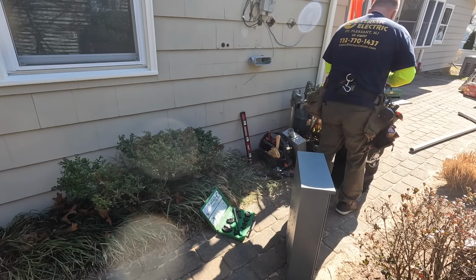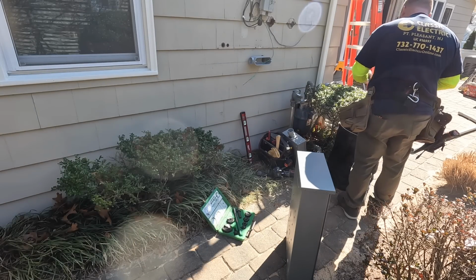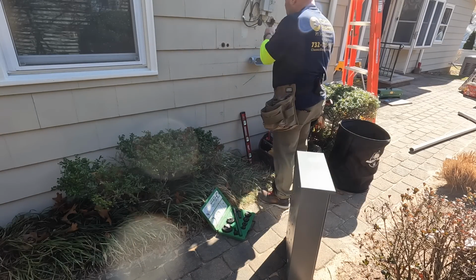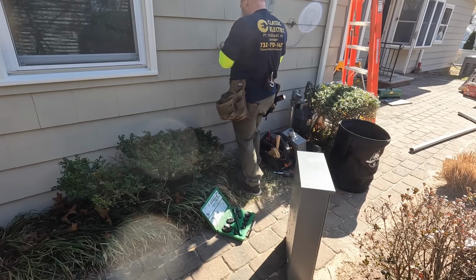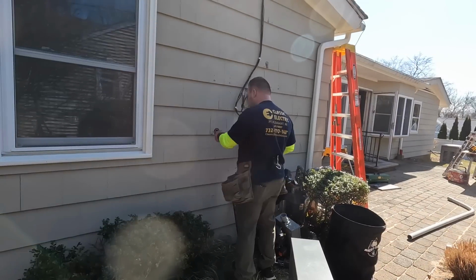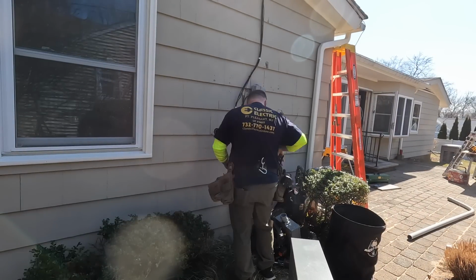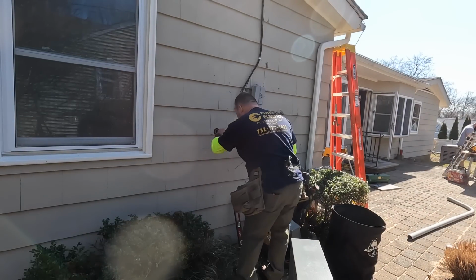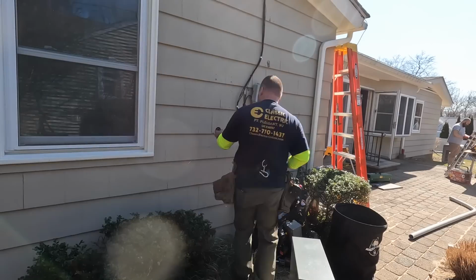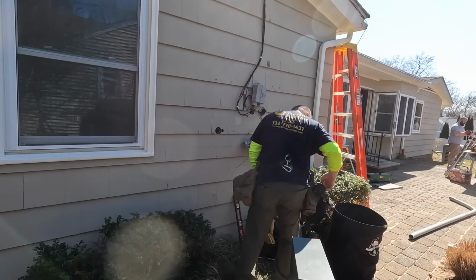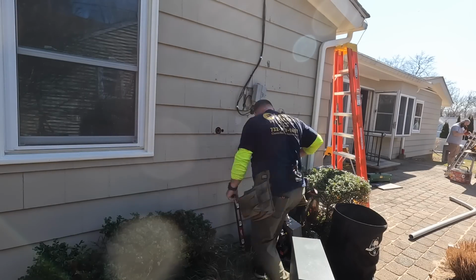So I wasn't planning on moving those anywhere, and I had to figure out where the knockout was going to be on this enclosure, where it's at a readily accessible height for the disconnect, and then of course where the conduit's going to leave that transfer switch going into the load, where the circuit breaker panel is on the inside, and then also a conduit for the meter. I had a good idea what I wanted to do, and it turned out just right.